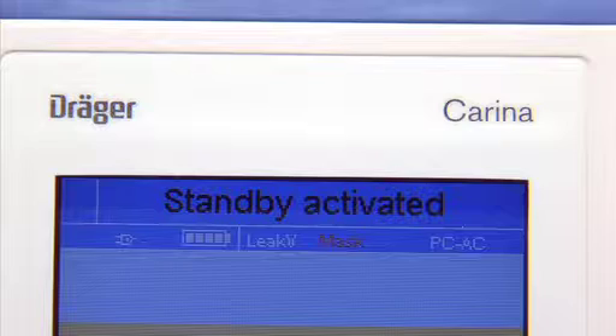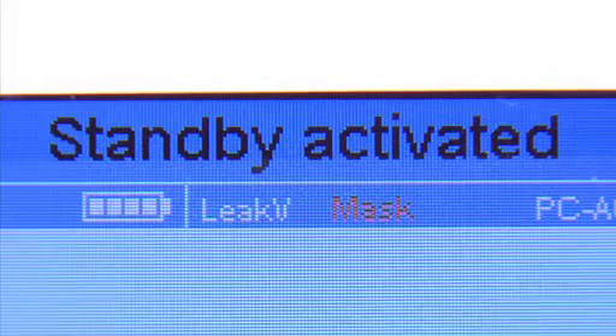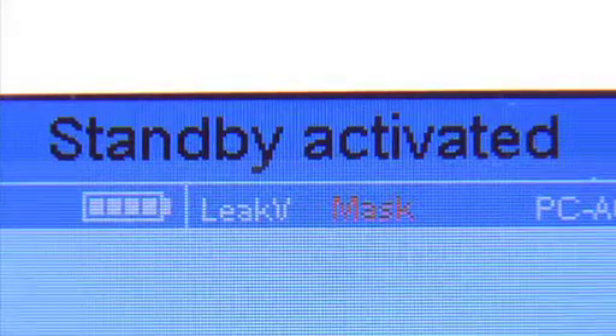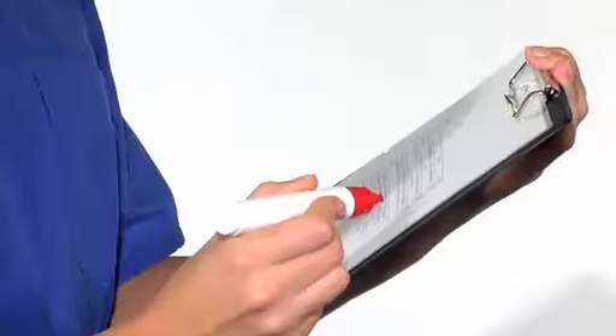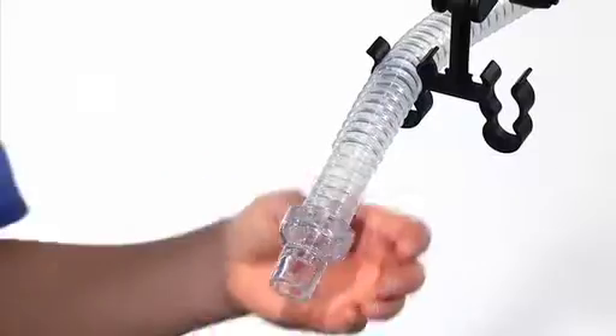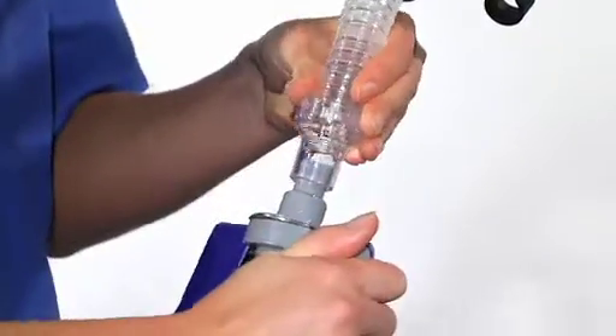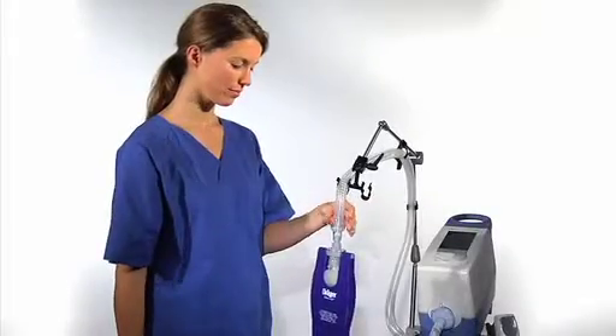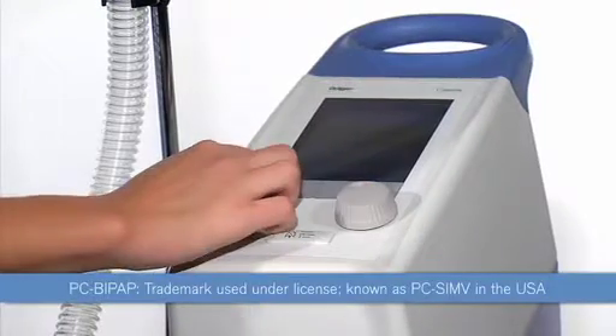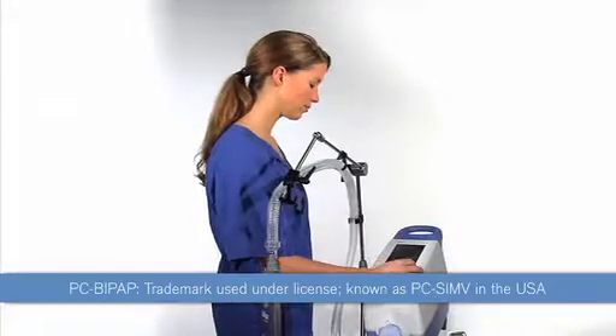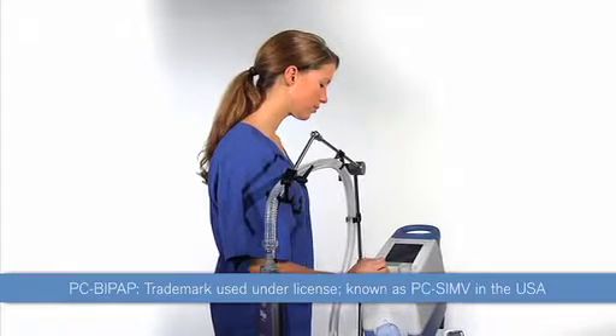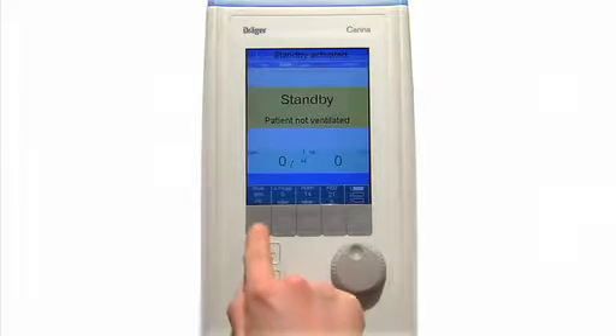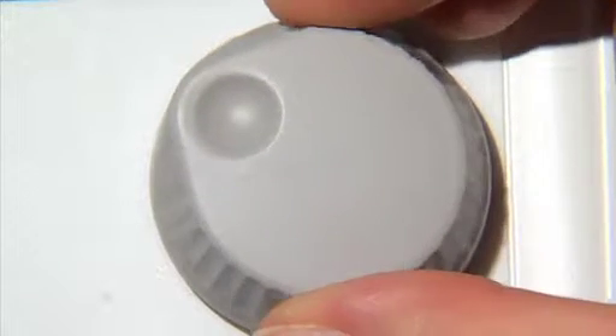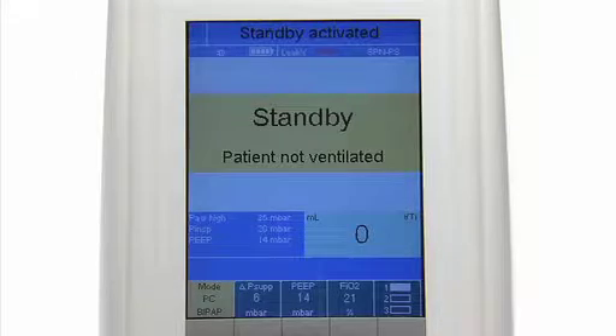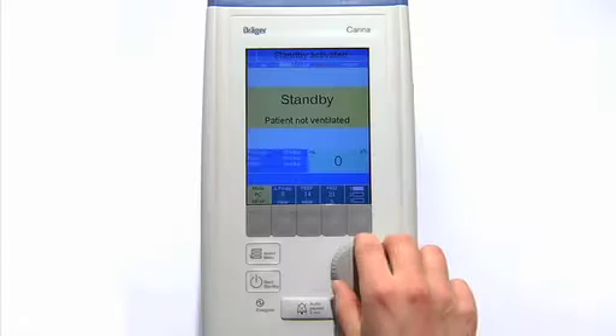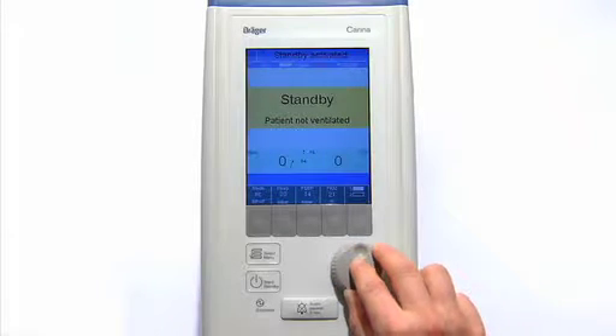Please check the patient connection mode in the status line. It can be set to mask or tube. If it doesn't correspond to the used type, please make the necessary changes. Connect the test lung to the patient circuit. Now set the mode PC BiPAP. In the US, this mode is called PC SIMV. To do this, press the button below the set mode and turn the rotary knob until you see PC BiPAP. Then press the rotary knob to confirm your choice.